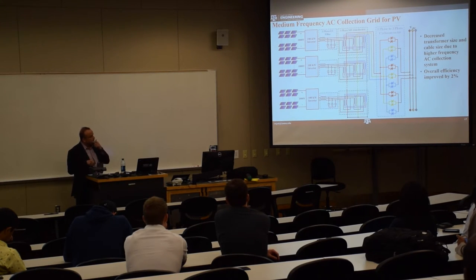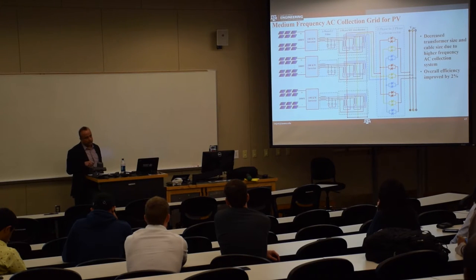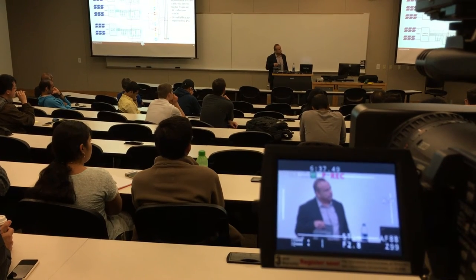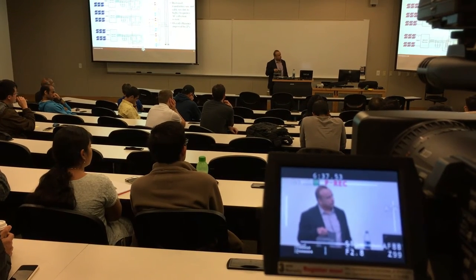So that was our investigation. We were concerned about the higher frequency cabling, and then we did quite a bit of modeling, using the actual lengths of the field. And then our overall conclusion was, if you do all this, it improves the efficiency by 2%, and also it actually decreases the size. Although you may say it's a big open field, the size may not matter, but not only do they have to put a lot of roads, they concluded that it could save some area, so you could actually put more solar panels. But more importantly, the cabling cost can go down, and the efficiency could improve.